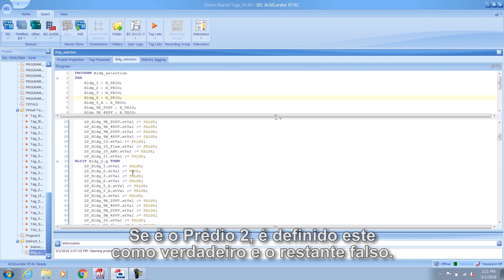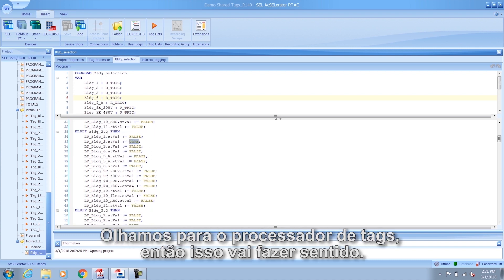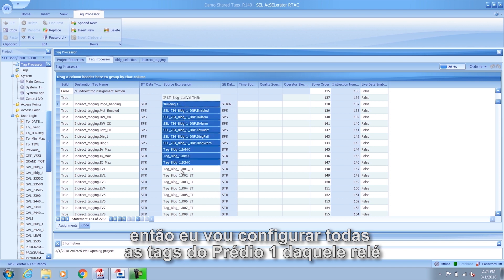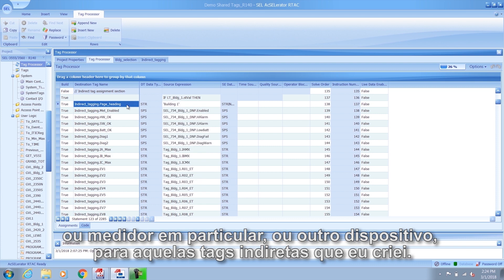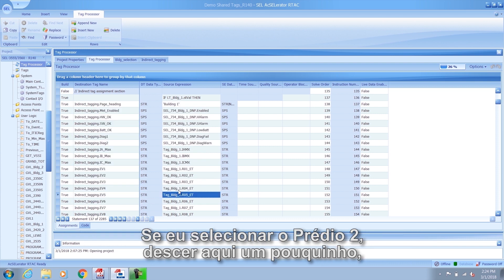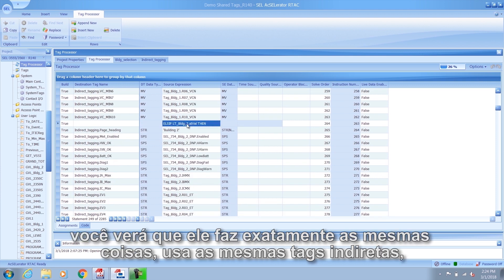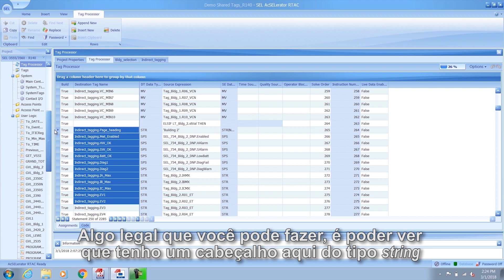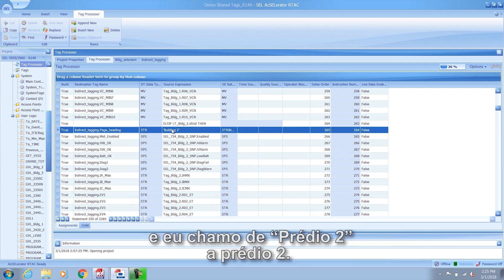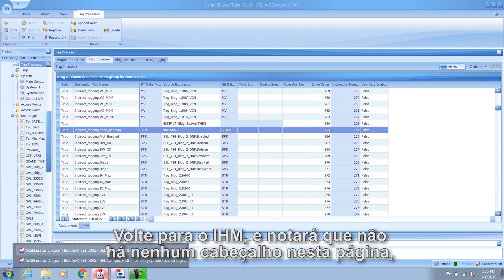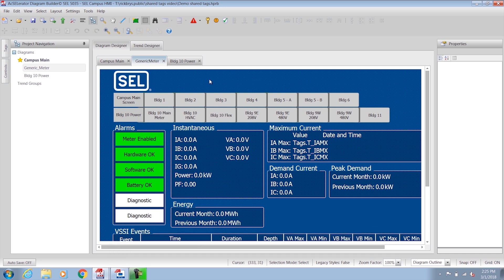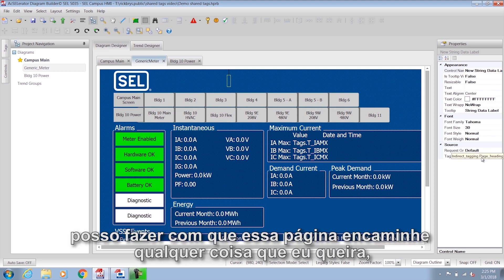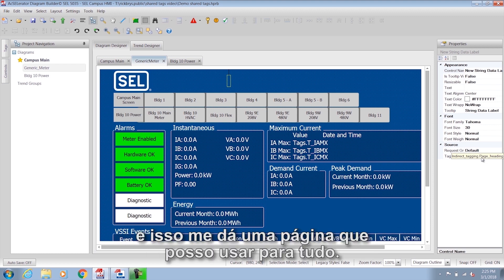If it's building 2, it sets that one to true and the rest to false. Looking at the tag processor, this makes a lot of sense: if building 1's latch bit is true, then all of the tags for building 1 from that relay, meter, or device are set to those indirect tags I've created. If I select building 2, it does exactly the same thing — uses the same indirect tags but with the specific tags for that device. You can also set a string-type heading tag, like 'building 2,' so back in the HMI the page heading is an indirect tag that can be changed on the fly, giving you one page you can use for everything.